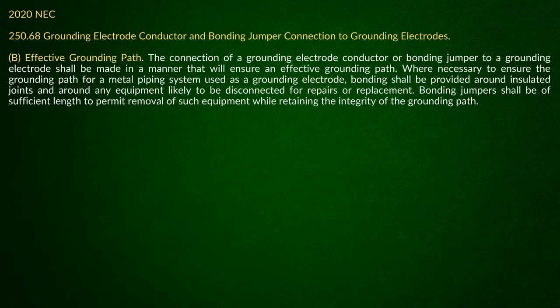Matter of fact, I just finished it the other night. I've been going through updating those illustrations, but what it says here: the connection of a grounding electrode conductor or bonding jumper to a grounding electrode shall be made in a manner that will ensure an effective grounding path. Where necessary to ensure the grounding path for a metal piping system used as a grounding electrode, bonding shall be provided around what? Insulated joints and around any equipment likely to be disconnected for repairs or replacement.